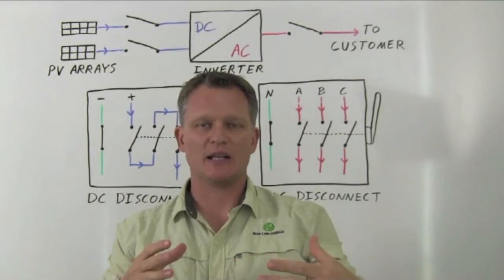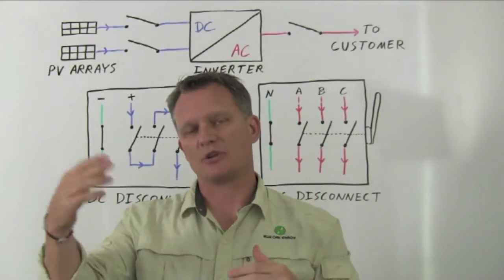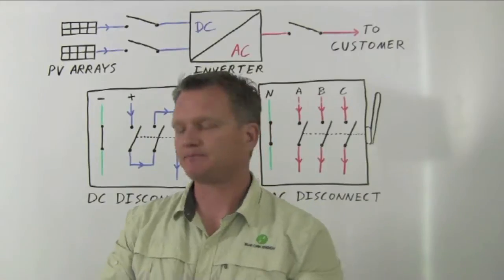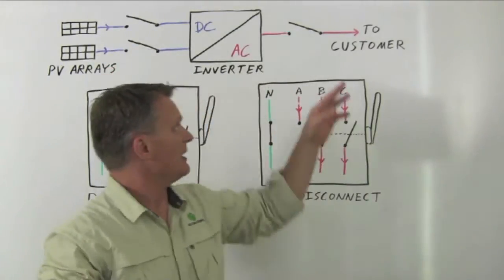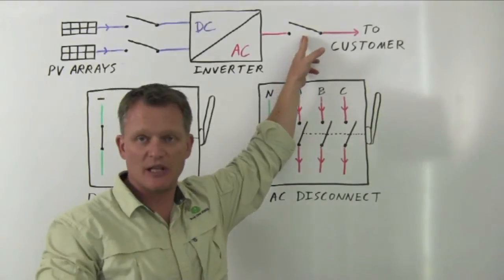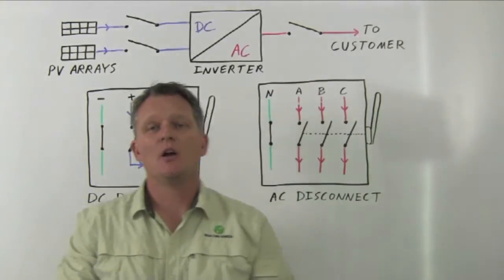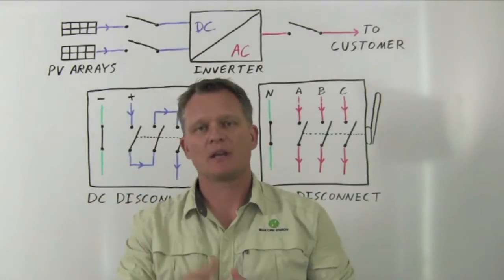Now, the reason we need disconnect switches is to isolate components of the system for safety and maintenance purposes. Here we're showing disconnect switches on the DC side and a disconnect switch on the AC side. When we want to break these circuits while the system is operating, we call that load break.